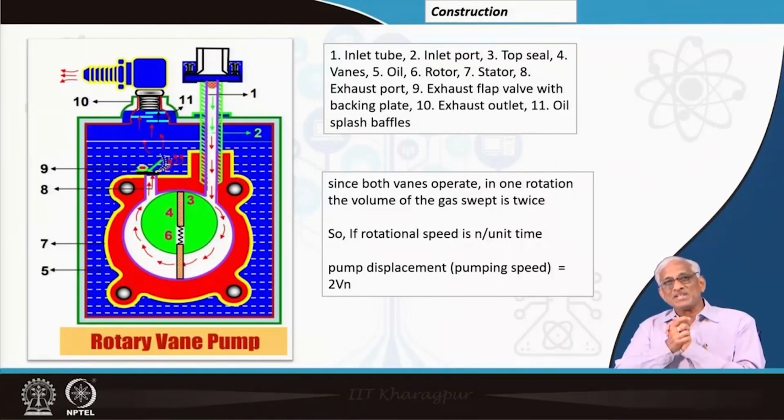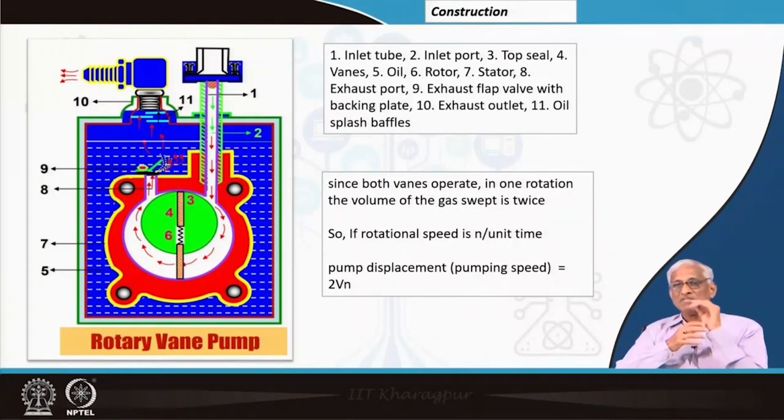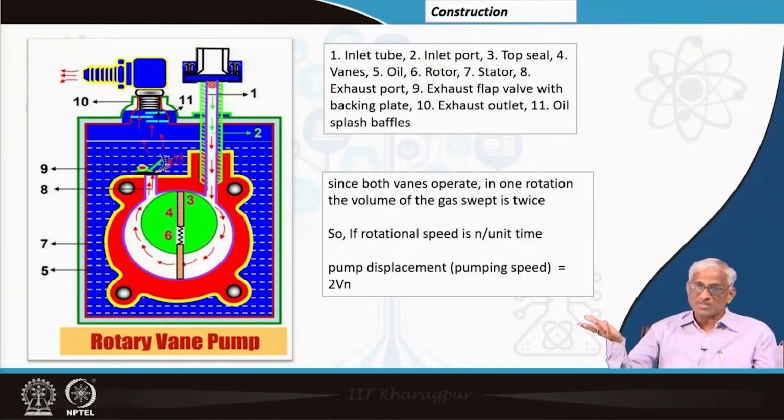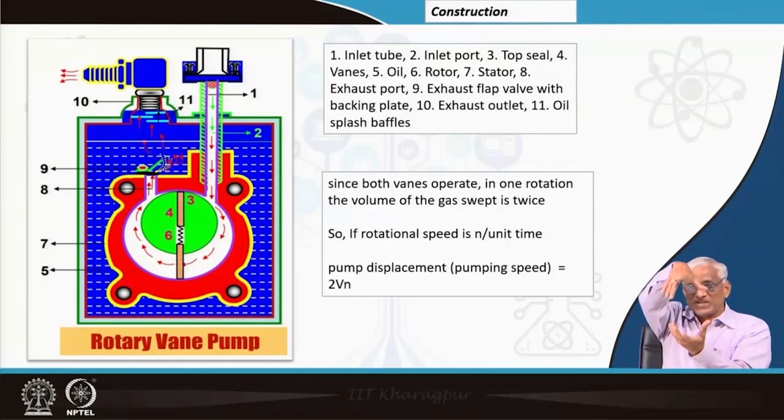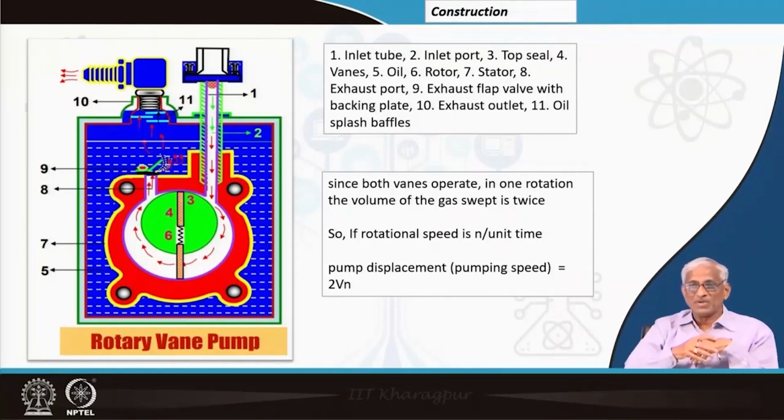So, in a working condition, there are three touch points, physically two touch points, but the third, the top seal, also looks like a touch point with an interface of oil. Three touch points in a rotary vane pump will create three volumes. If it is concentric, there will be top and bottom, two annular structures, two moon-like structures in the annular gap.